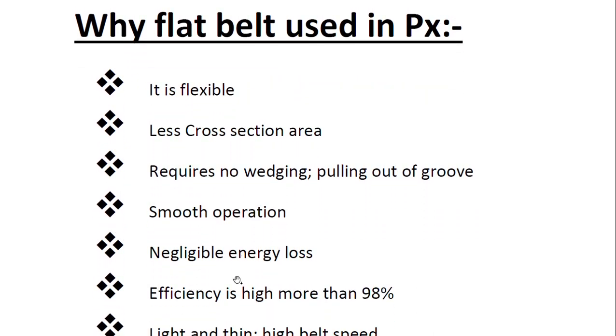The flat belt is flexible and has less cross-section area. It requires no wedging or pulling out of the groove. With V-belts, you need to pull and tension them, which requires maintenance. Over time the V-belt becomes loose and there are chances the belt will break. The flat belt provides smooth operation with no such issues.